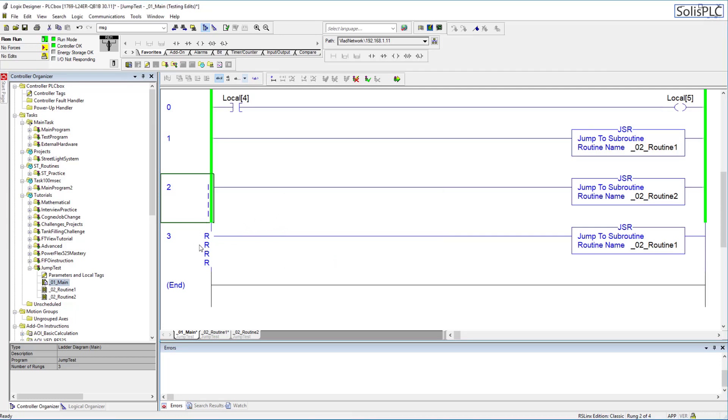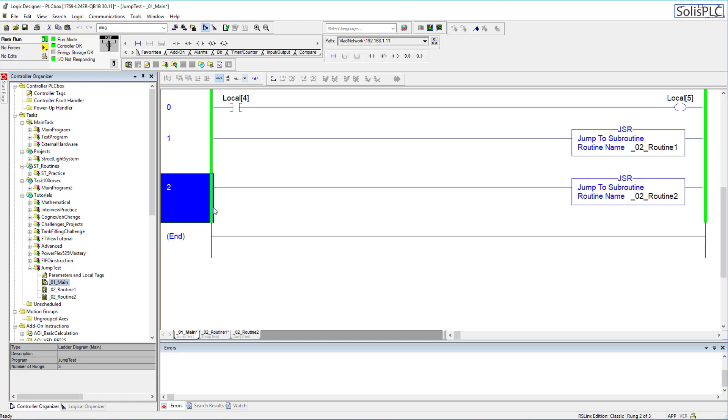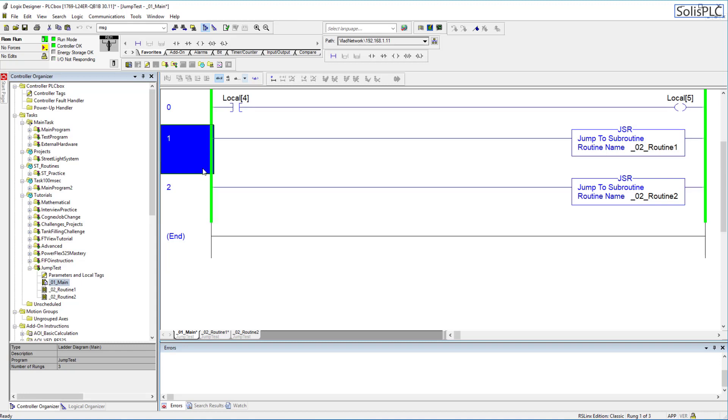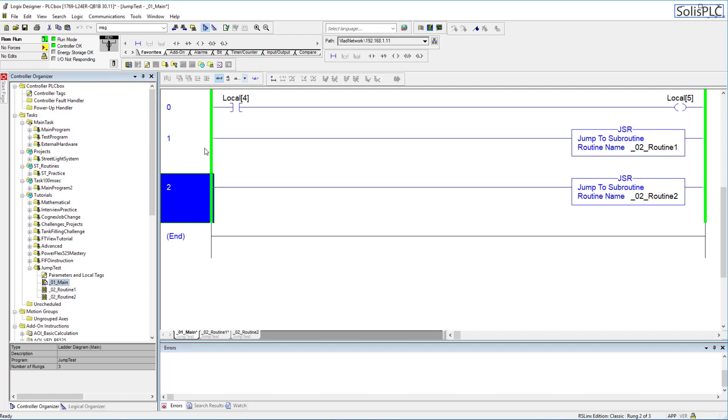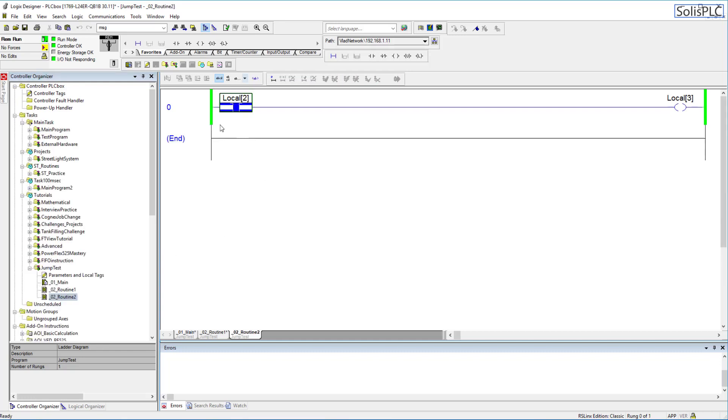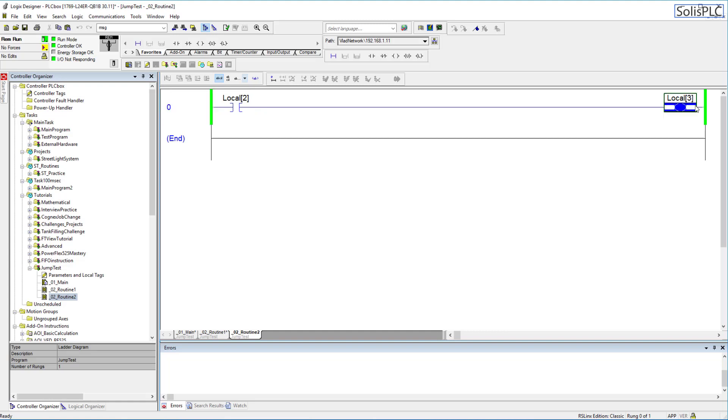Now after you've committed there's no way to go back and essentially if you've made a lot of changes in that same rung there's no way to go back to the previous version of the rung because it's simply not stored by the PLC anywhere else. So once you've overwritten completely then you've committed to that new change and at this point if you wanted to go back you'd have to re-edit the rung. Now that being said I've added routine 2 so let's go back into routine 2 and double check what's going on. As you can see the rungs are now green on either side which means that we are calling this routine and of course if I toggle this logic it is going to execute the OTE as I would expect.